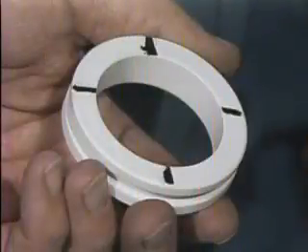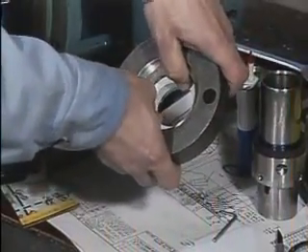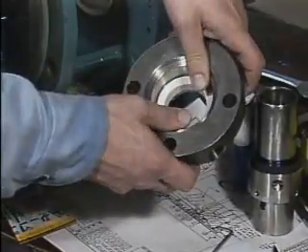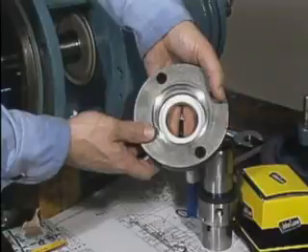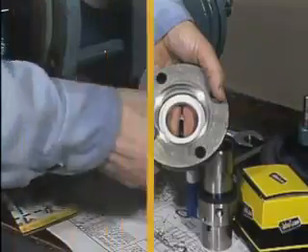The mating ring has a polished side and an unpolished side. Most manufacturers mark the unpolished side of the ring to distinguish it from the polished one. The mating ring is inserted into the gland plate so that the unpolished side goes in first. Inserting it this way allows the polished side to face toward the rotating seal face when the rotating element is installed.